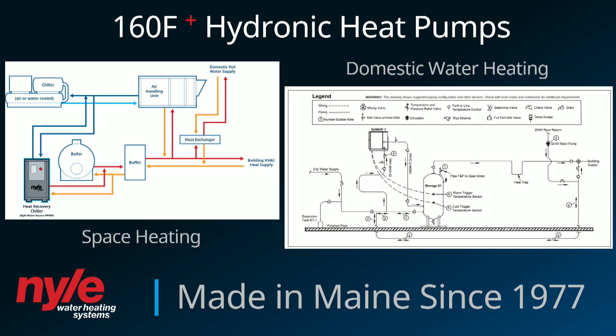We specialize in manufacturing heat pumps that produce 160 degrees and above. If you need hot water, we classify 140 and above as our sweet spot for heat pump engineering and the applications that fall under those temperatures. To preface the other folks who will be talking about a myriad of technologies in this space, we will cover both space heating and domestic hot water in commercial applications. Once you leave the residential realm, domestic hot water typically needs to be stored at 140 and above to satisfy building code. That's a health and safety matter and not something to shirk away from - we need to satisfy those demands.